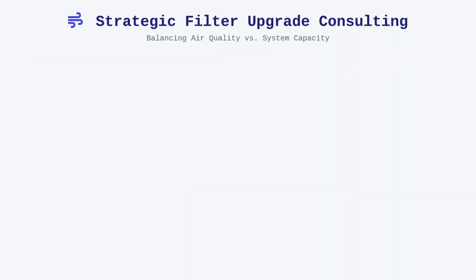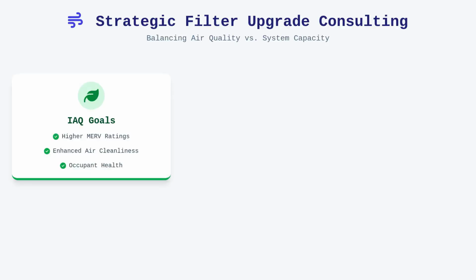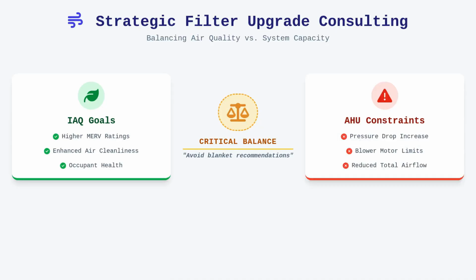When you are consulting with clients regarding potential filter upgrades, you must balance their indoor air quality goals against the capacity constraints of the existing air handling unit. A common pitfall is the blanket recommendation of a higher MERV-rated filter without first verifying the system's ability to handle the resulting increase in pressure drop. If the blower motor is already operating near its limit, installing a dense, high-efficiency filter will likely trigger a reduction in total system airflow, leading to poor thermal distribution and potential coil freezing in cooling applications. Instead, suggest upgrades that maintain manageable pressure drops while targeting the specific particle sizes relevant to the building's occupants.